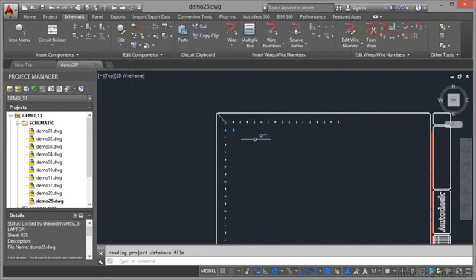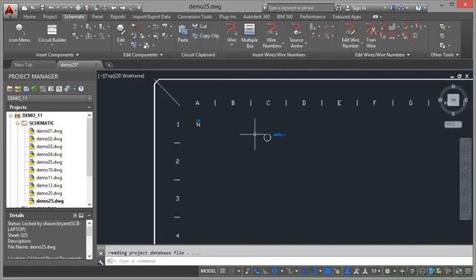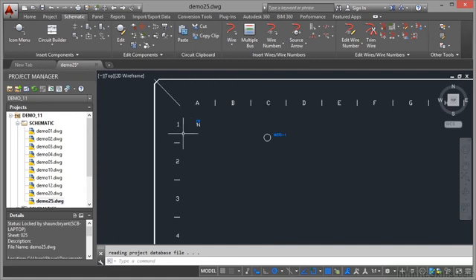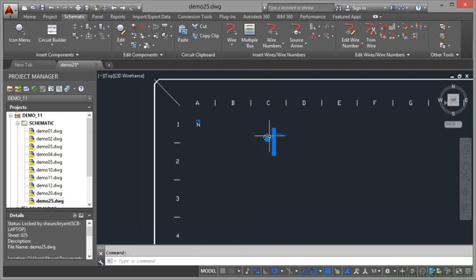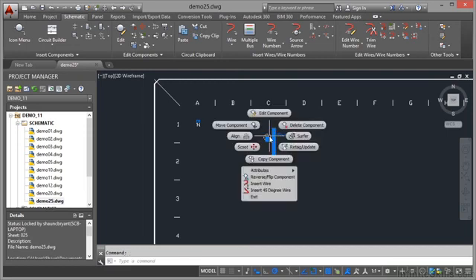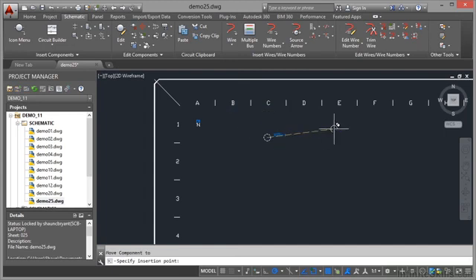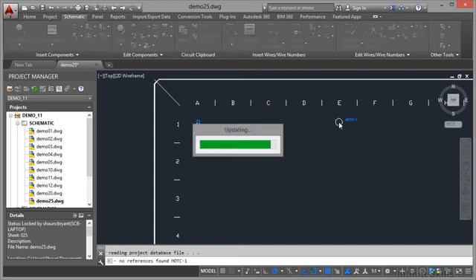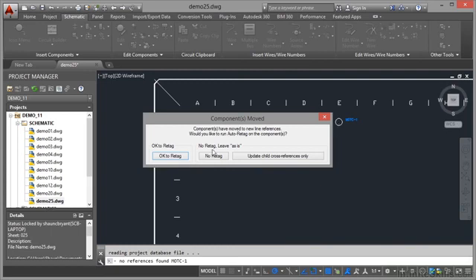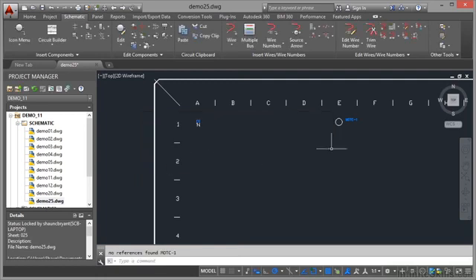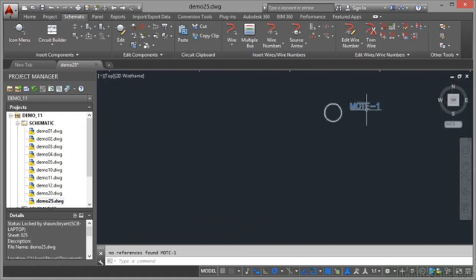And we'll drop that say there. Can you see there MOT C1, just click on OK there. And if I zoom in now there's the C there's the one, motor C1, can you see it's picked up that grid reference. So if I now move that component, so I'll click on it right click and I'll move that component over here to E1. What will happen is it will update and now it's saying would you like to run auto re-tag on the component? Now I do need to re-tag it because it's in a different place on the grid. So if I OK to re-tag that and I zoom in it's now E1.